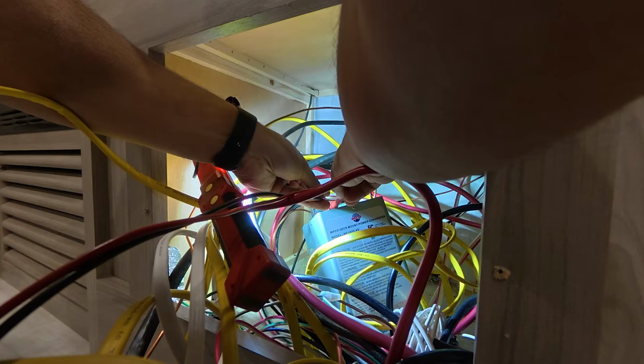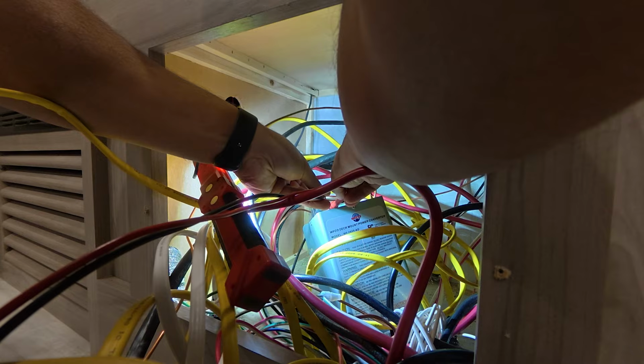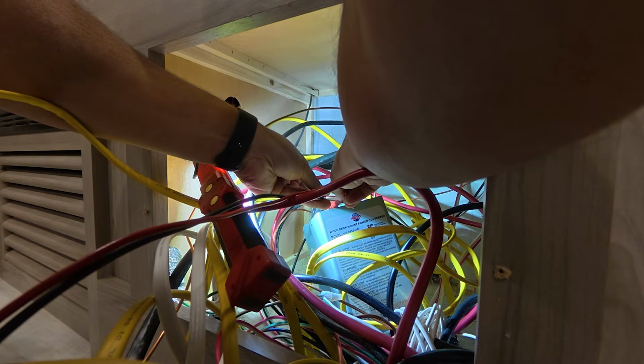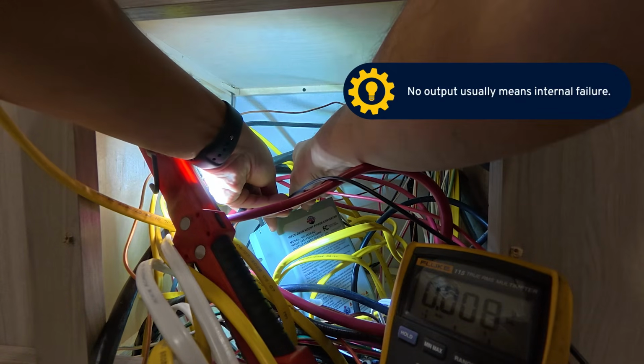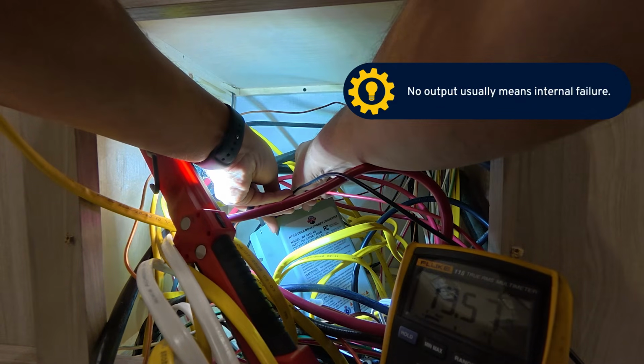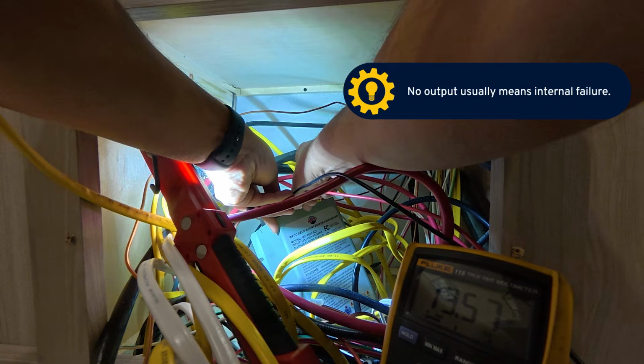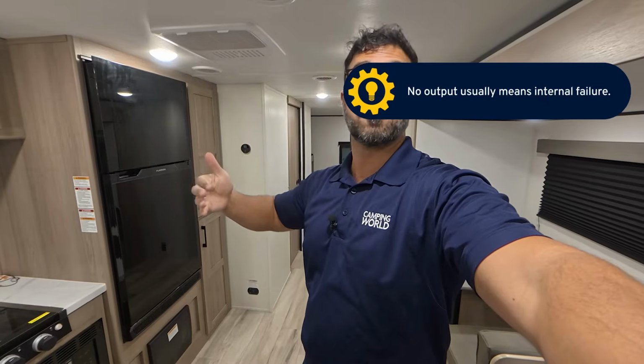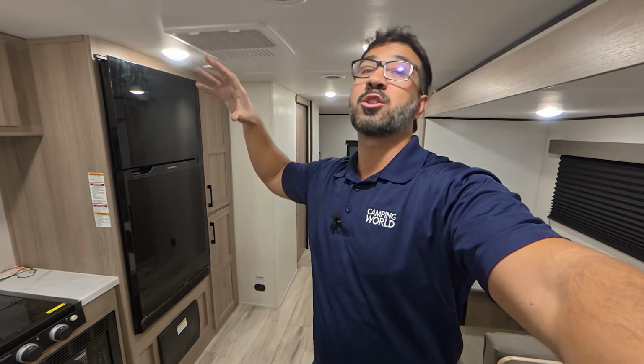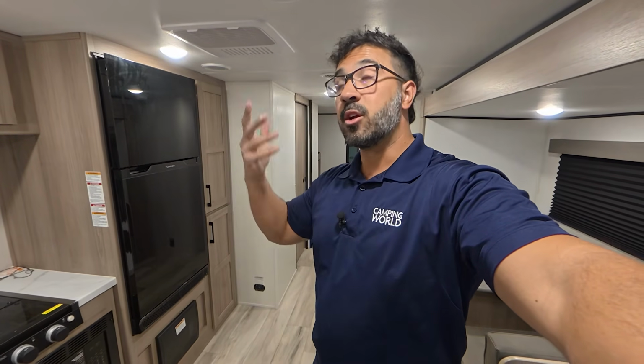With those safety steps noted, a healthy converter output should read somewhere between 13.6 and 14.4 volts DC once we plug back into shore power. When you add a load, that measurement should remain stable between 13.6 and 14.4. If the voltage drops significantly or fluctuates wildly under a load, your converter may be failing, but additional inspection by a certified RV technician can be helpful for the most accurate diagnosis.